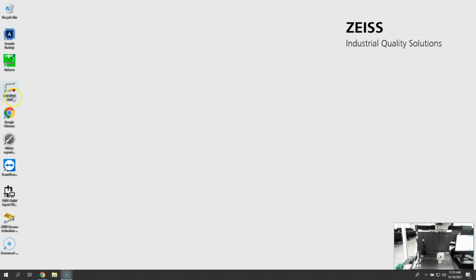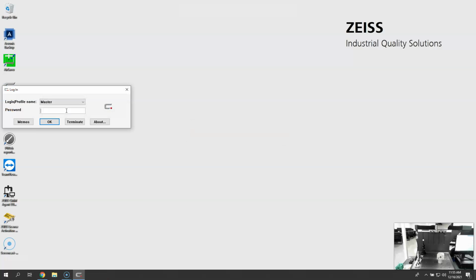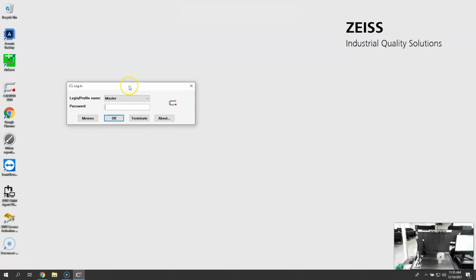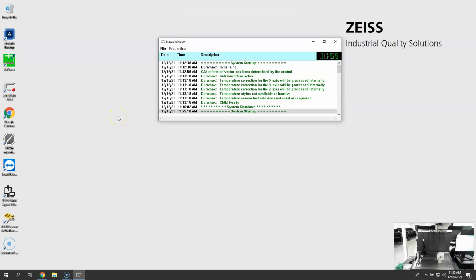Alright, so in the meantime I will double click to open Calypso. Now I intentionally did not turn on Calypso yet because when I say OK to this login dialog, there is no password here. The status window will pop up, and then the machine will automatically let me know that the CMM needs to be homed. Alright, so you want to have the controller on, you want to have the drives on before you open Calypso.